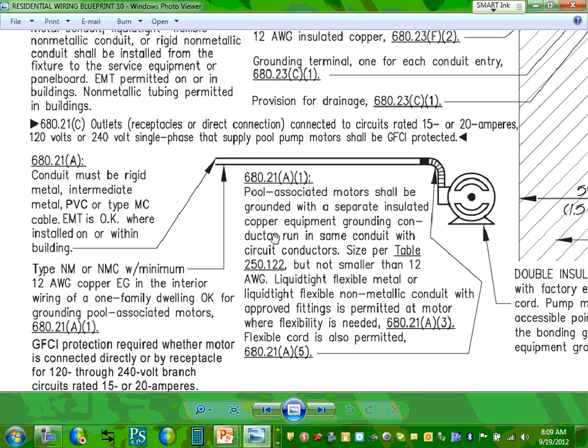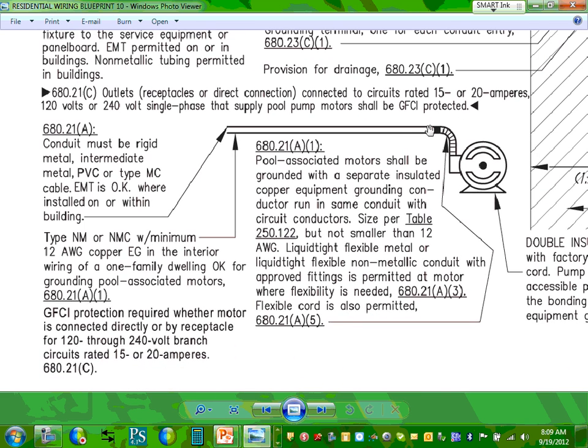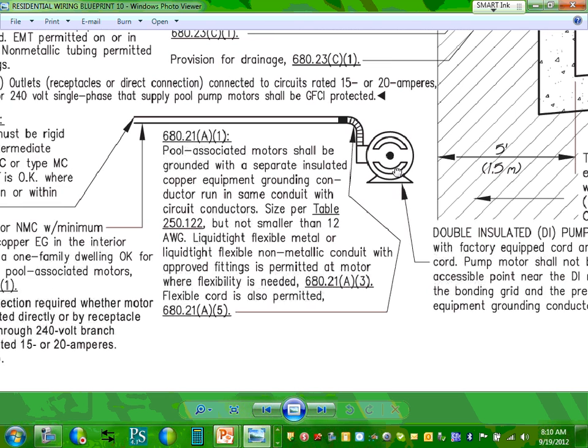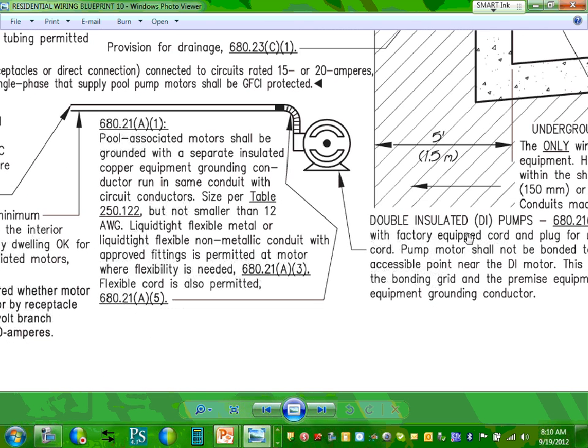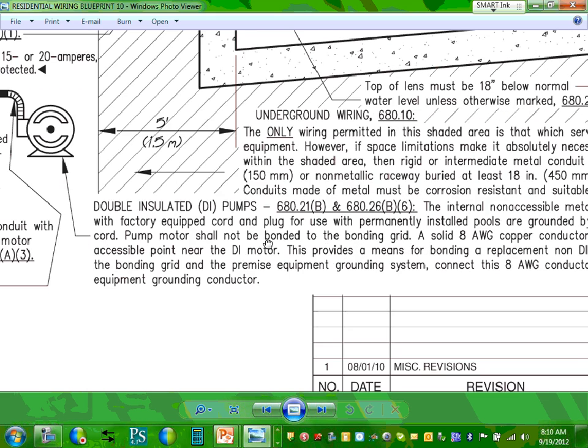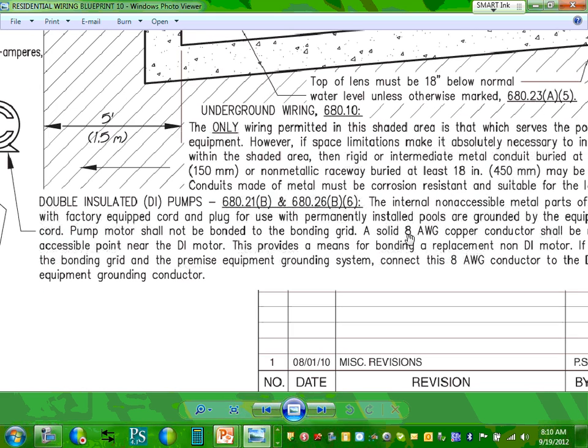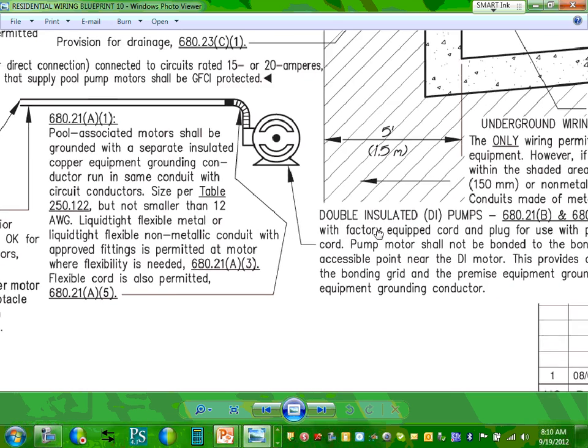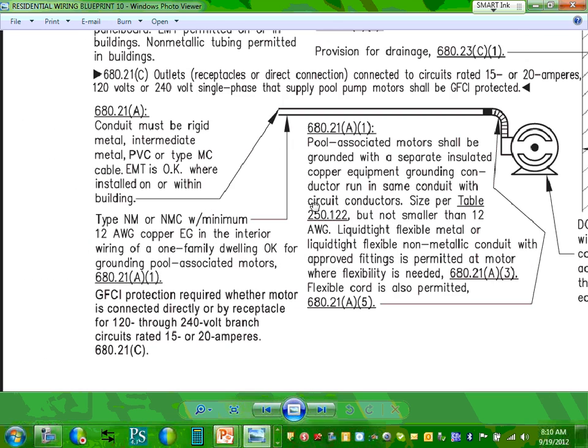If you look at the motor here, look at that one tying to this motor, conduit must be rigid to tie to this. This is a double insulated pump. If you have a double insulated pump, you still have to provide a number 8 conductor. Can you guys see the number 8 conductor right here for grounding? There are a few things, and you can use PVC, MC cables, and so forth.